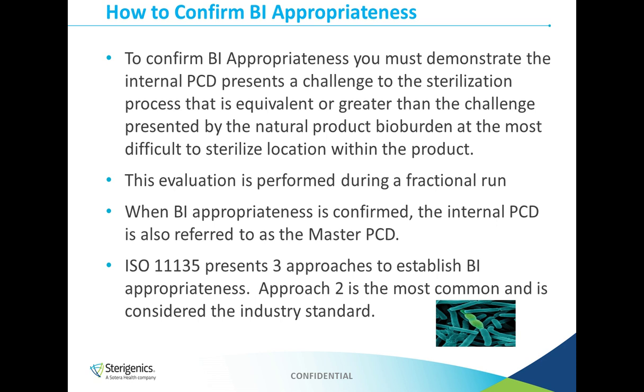So in other words, that spored product that you have has to be more challenging than the natural product bioburden on any device that you have in your product line. And this evaluation, again, is performed during fractional runs. And when you do confirm BI appropriateness with a specific internal PCD, that internal PCD is now referred to as the master PCD. Now, ISO 11135 presents 3 approaches to establish BI appropriateness.